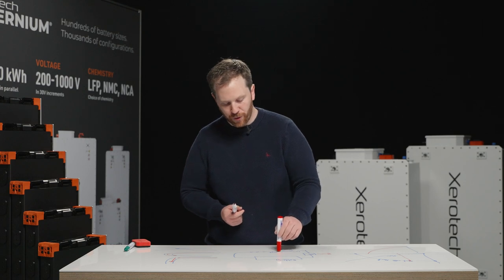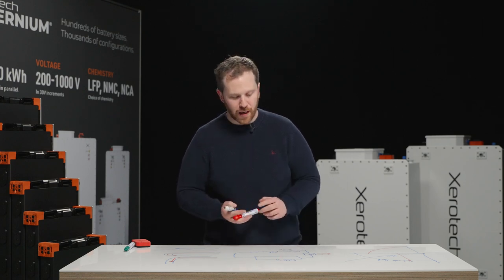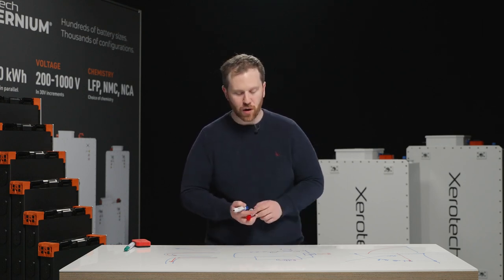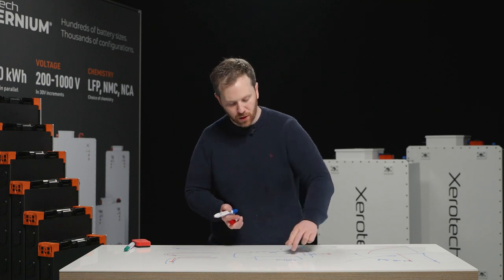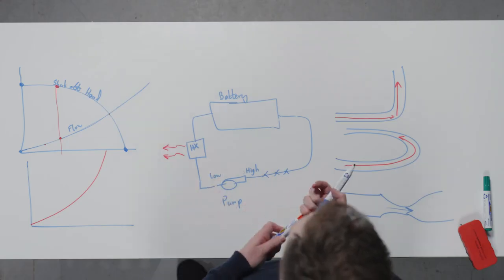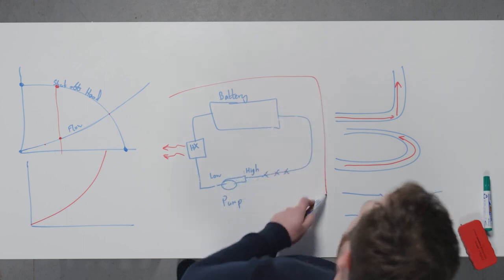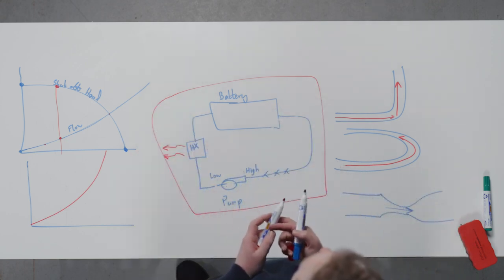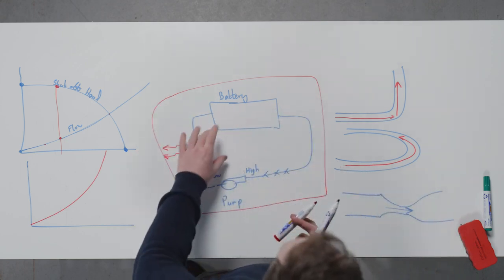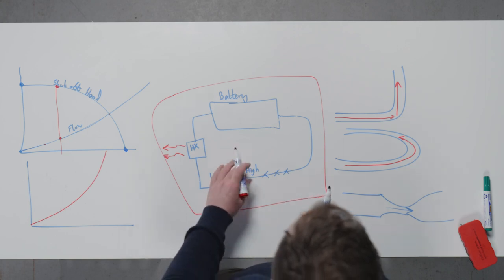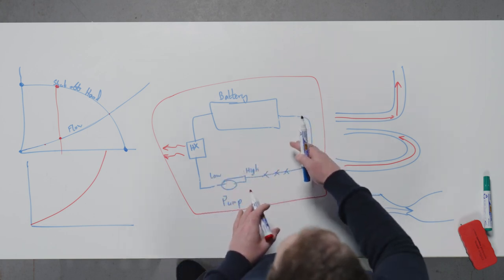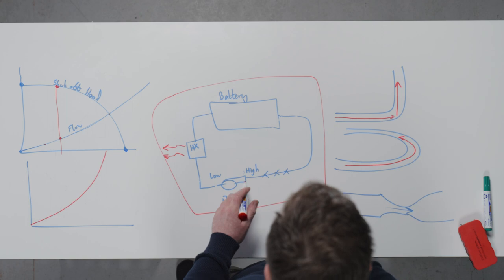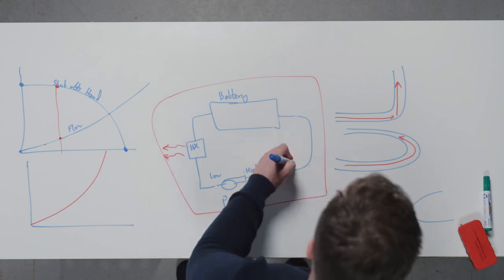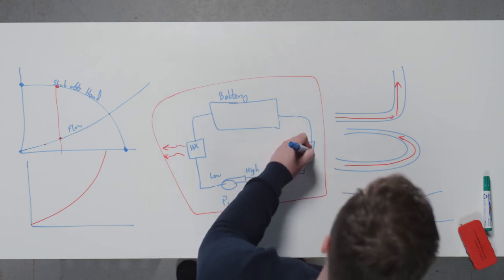Another consideration for a Xerotech battery system is that we always want to make sure that the battery is on the suction side of the pump. So what we've shown here would not be the ideal position for a Xerotech battery in a cooling system. So every component, including the hoses, has pressure drop in it. But more importantly, large components have higher pressure drop.